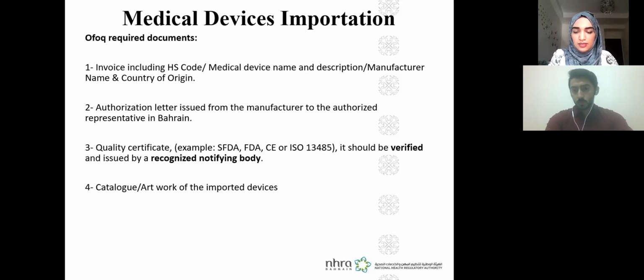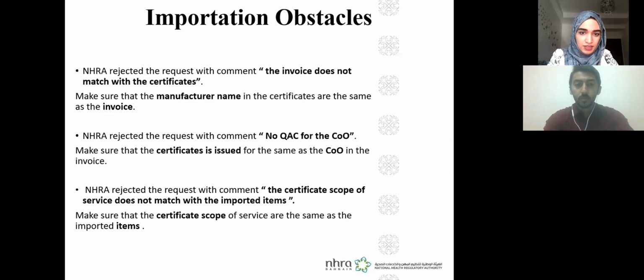Yes, my question is from my experience. For example, the supplier, the brand is from Italy and manufacturing in China, and in the certificate, CE and whatever it is, they are mentioning the Italian name. Is it acceptable? Well, you need to rephrase your question in terms of legal manufacturer and physical manufacturer.